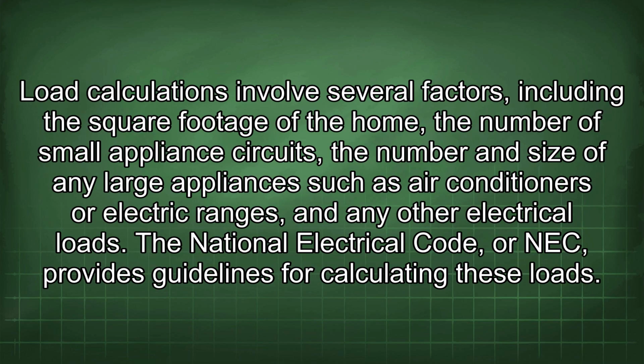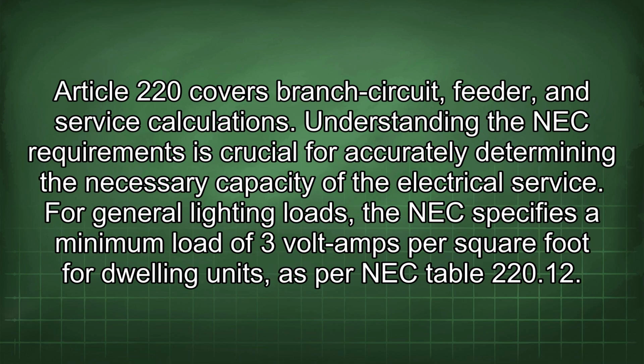Load calculations involve several factors, including the square footage of the home, the number of small appliance circuits, the number and size of any large appliances such as air conditioners or electric ranges, and any other electrical loads. The National Electrical Code, or NEC, provides guidelines for calculating these loads. Article 220 covers branch circuit, feeder, and service calculations. Understanding the NEC requirements is crucial for accurately determining the necessary capacity of the electrical service.